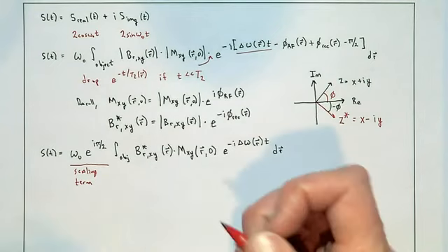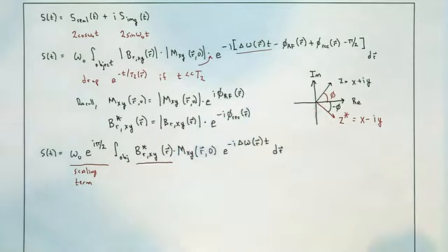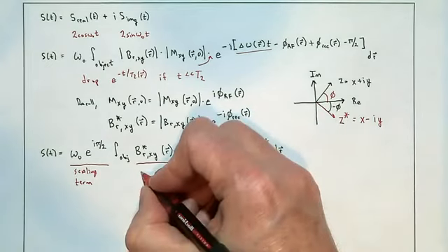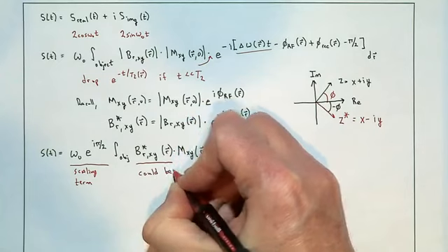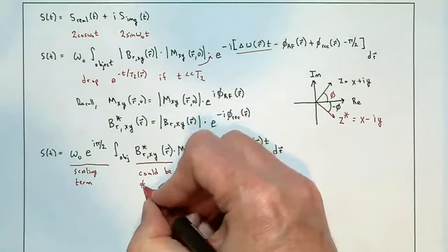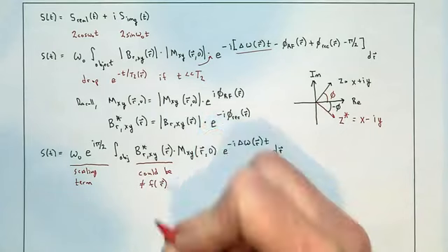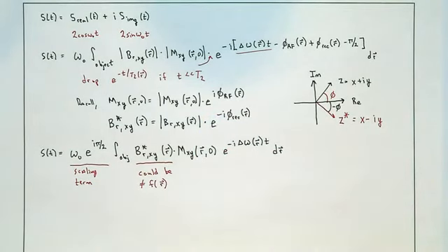This term here, the B field from the receiver system itself or the coil itself, it's definitely possible that this could be, let's say, not equal to some function of space. By that, I just mean you have such a good coil or a small field of view adjacent to that coil that in some volume of interest or region of interest, the spatial variation is unimportant. Not a great assumption, not true of most imaging systems. But if we want to simplify our lives, it's a perhaps reasonable thing to do.